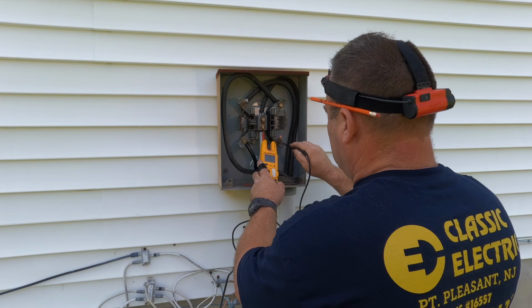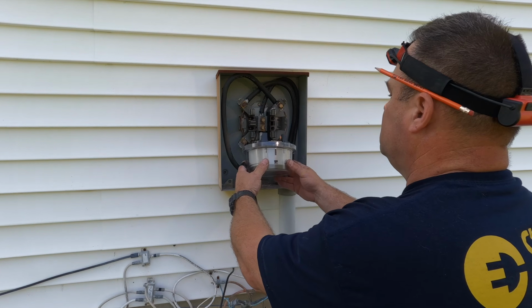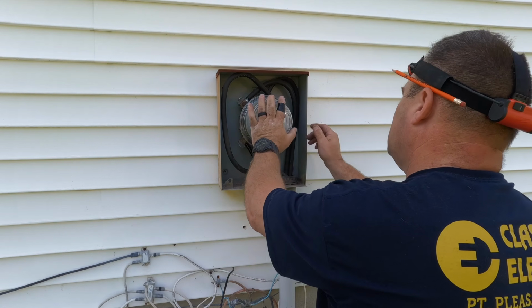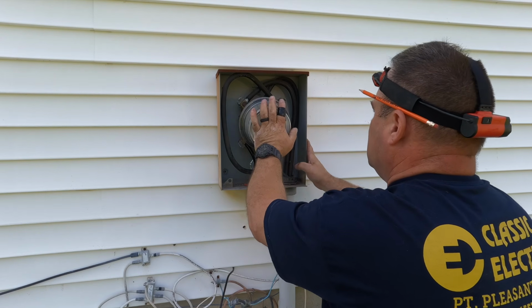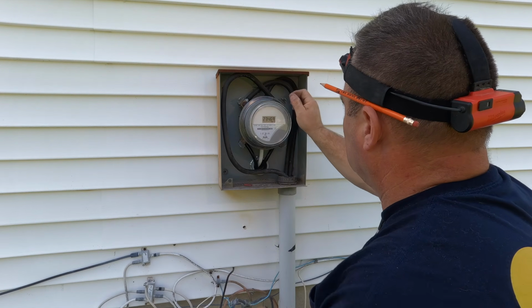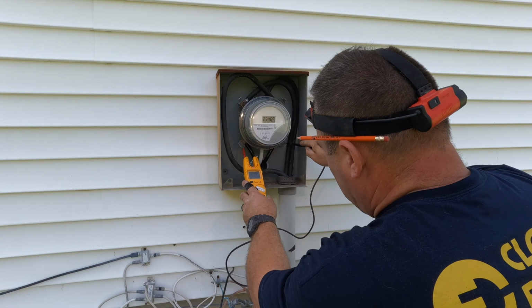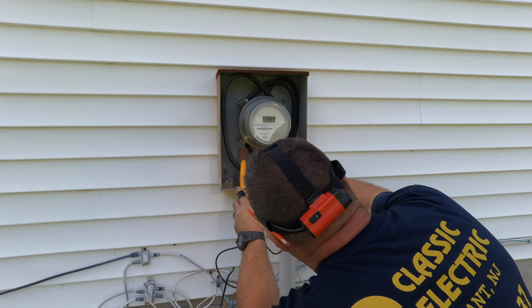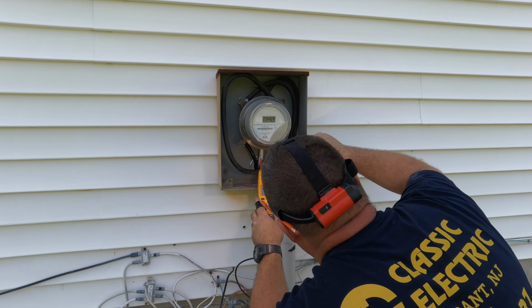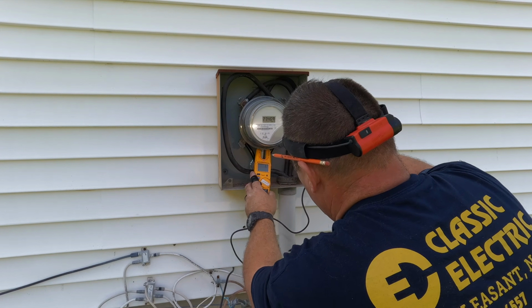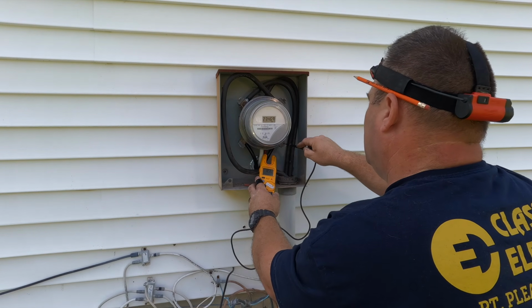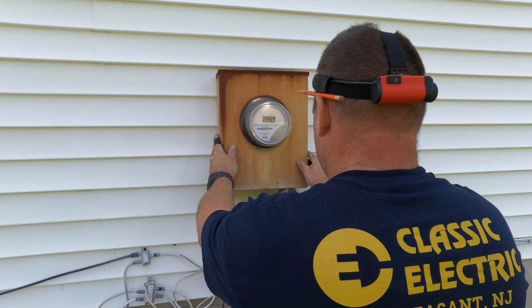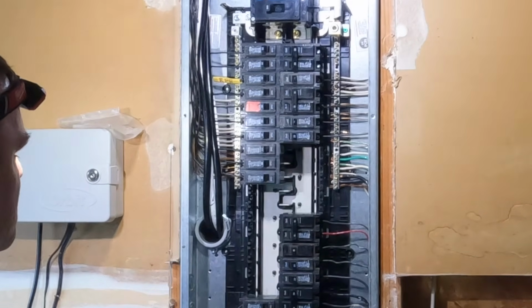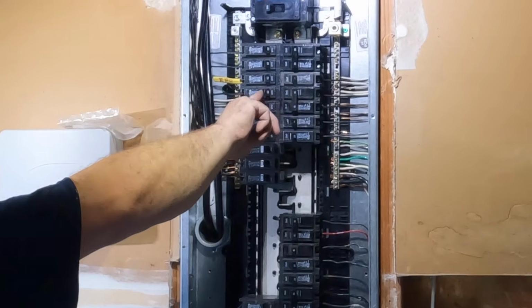So once I'm all done, I'll check for any shorts in my new conductors, and then I'll push the meter in, and then I'll come back and verify the voltage once the meter's in: 240 from leg to leg, and then 120 volts from each leg to ground. Now we're good. We put the cover on. Once I get back to the panel, I make sure there's power there. That's correct, 240 volts. Throw your main, turn on the individual breakers, and you're back online. Your customer's got power again.